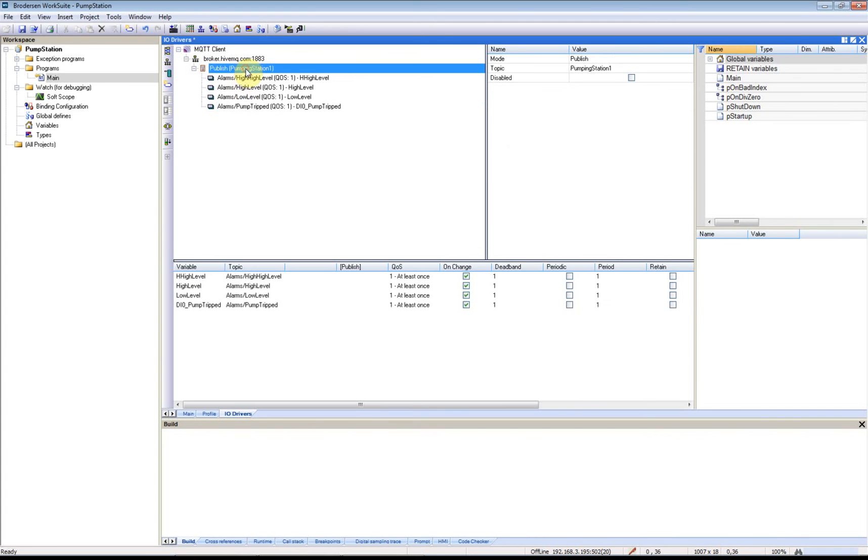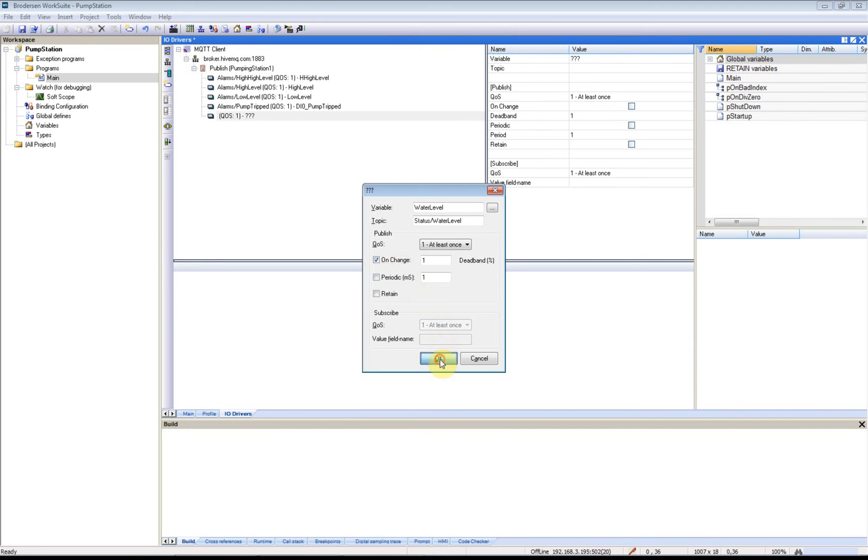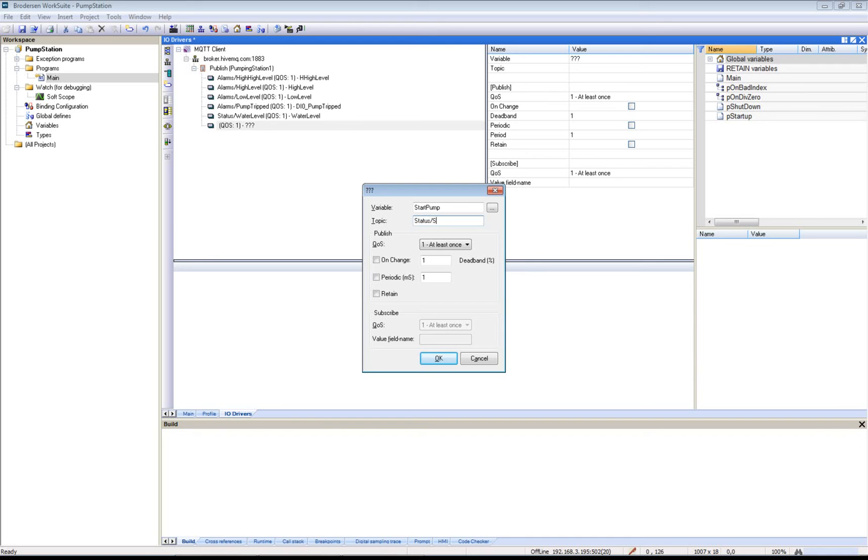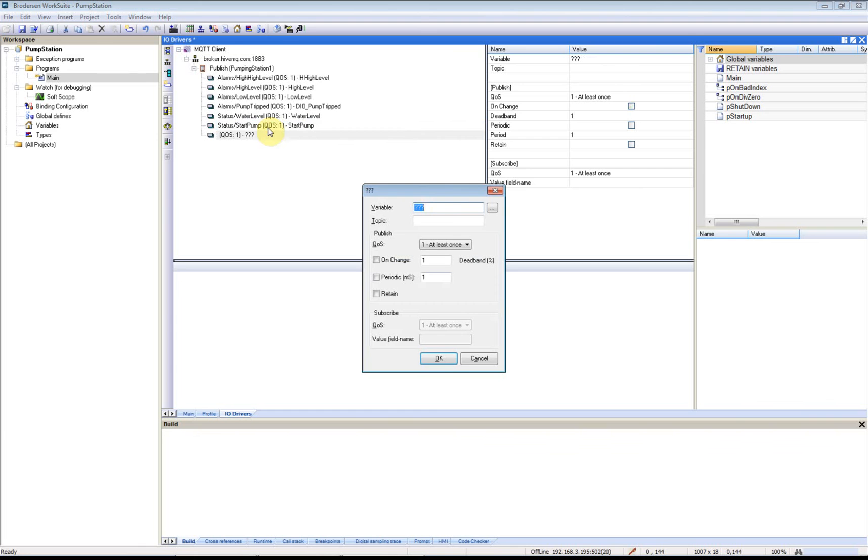Now I'll add some events for status messages. These are our water level, the analog value. We will have the topic Status Water Level, one percent change when to send the messages. Now I will have our Start Pump signal, so that will be Status Start Pump, and Stop Pump, Status Stop Pump.